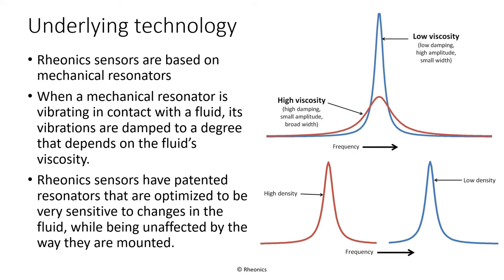Rheonics sensors are based on mechanical resonators. When a mechanical resonator is vibrating in contact with a fluid, its vibrations are damped to a degree that depends on the fluid's viscosity. The upper figure shows the resonance curves of how a resonator's damping changes with fluid viscosity — these curves show the amplitude of the resonator as a function of frequency. As viscosity increases, the extra damping reduces the size of the response, but also increases the resonator's bandwidth. When a resonator is moved from a fluid with a lower density to one of a higher density, its resonance frequency decreases in proportion to the fluid's density, as shown in the second figure.